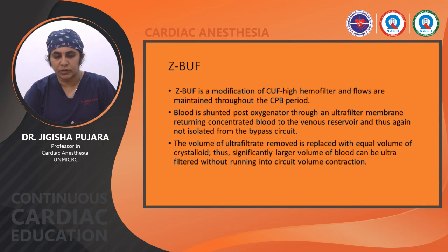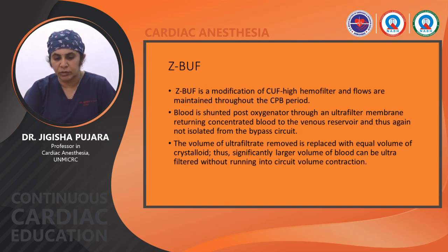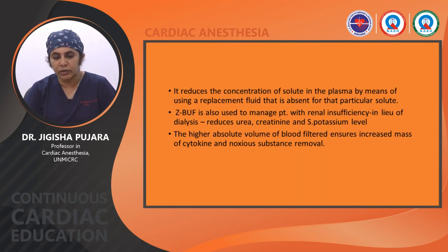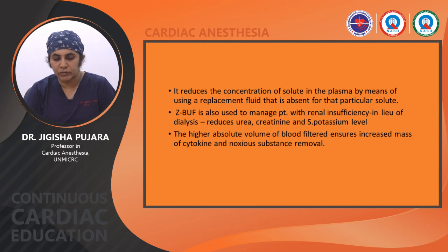Z-BUF is a modification of CUF. High hemofilter flows are maintained throughout the CPB period. Blood is shunted post-oxygenator through an ultrafiltration membrane returning concentrated blood to the venous reservoir; the volume of ultrafiltrate removed is replaced with an equal volume of crystalloid — Plasmalyte, Ringer's lactate, dialysate, or sodium chloride. This allows significantly larger volumes of blood to be ultrafiltrated without circuit volume contraction. It reduces the concentration of solutes in the plasma and is also used to manage patients with renal insufficiency, reducing urea, creatinine, and potassium levels.